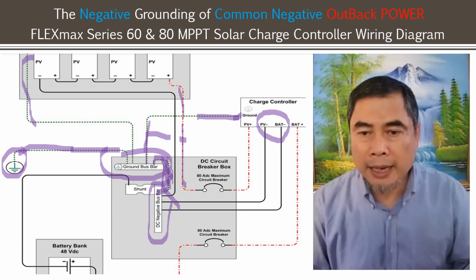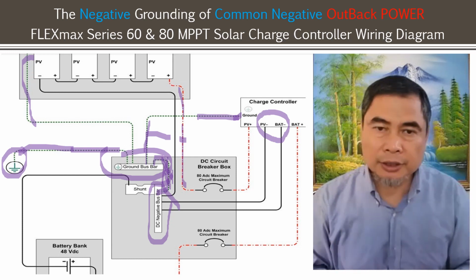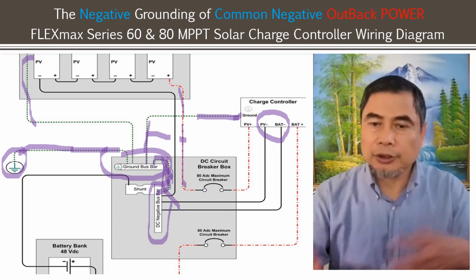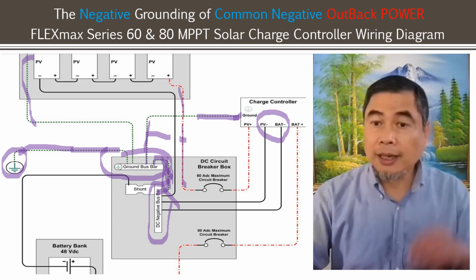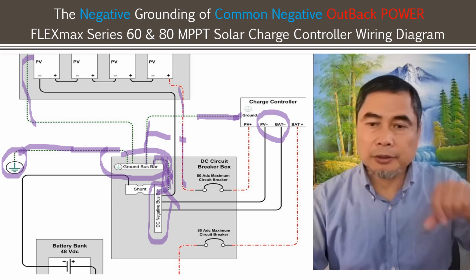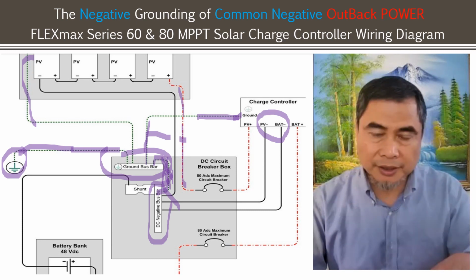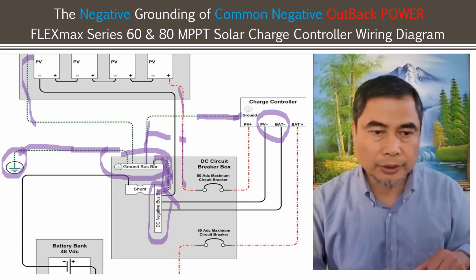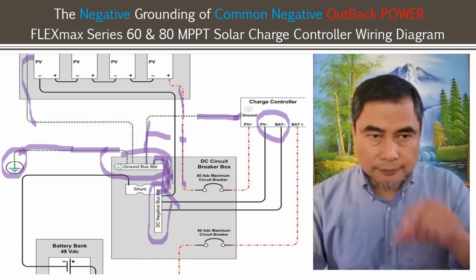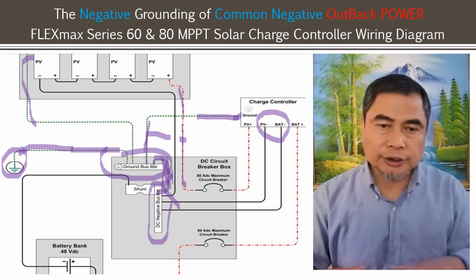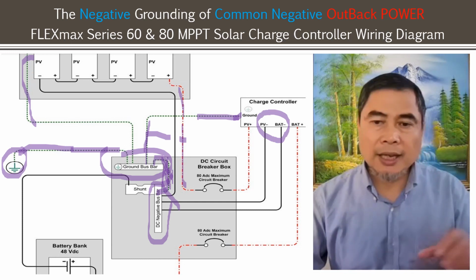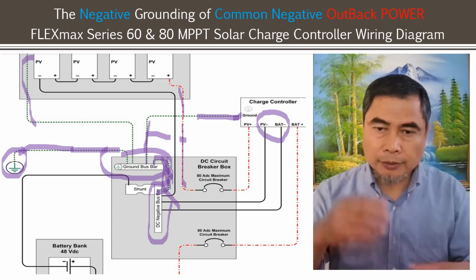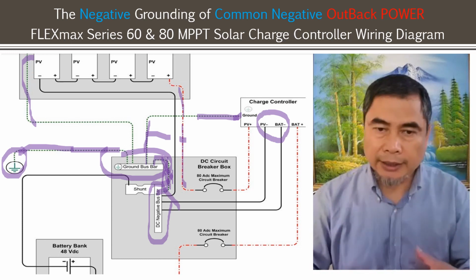Then you will have no power to the MPPT solar charge controller. It's all like a short circuit, and the current has to be limited by the solar panel itself, and that can be risky. And then the circuit breaker has to work. So just make sure you know which design you are using. You can't have both, okay? PV positive or PV negative.